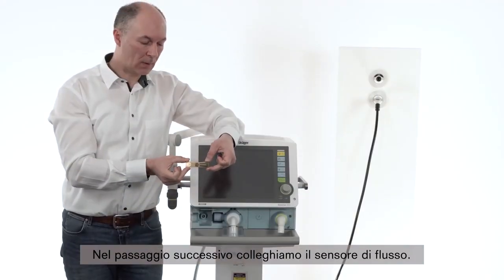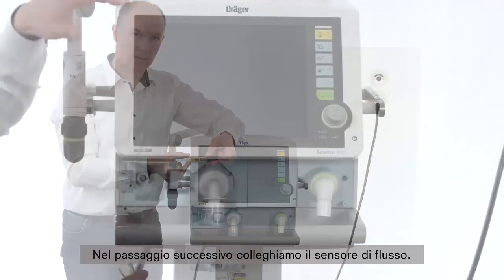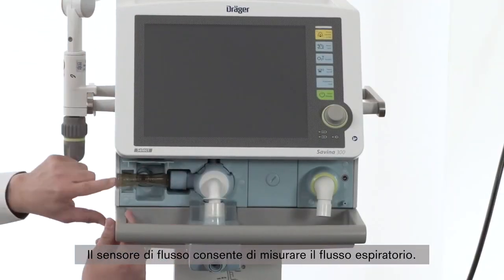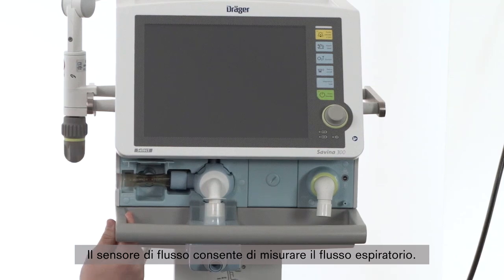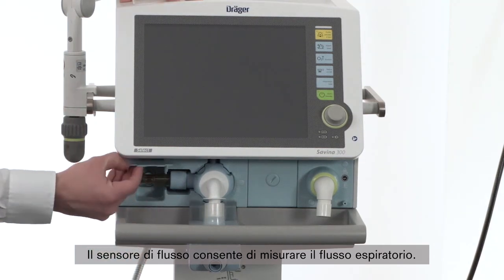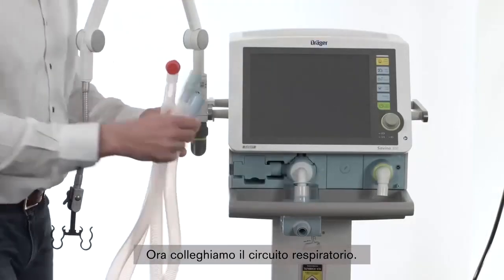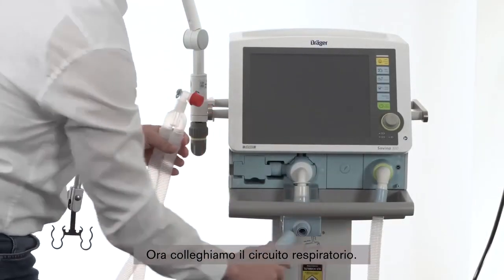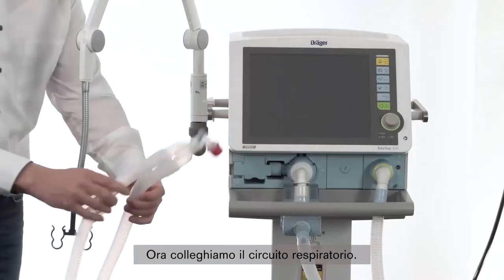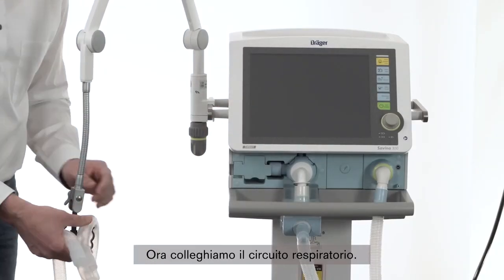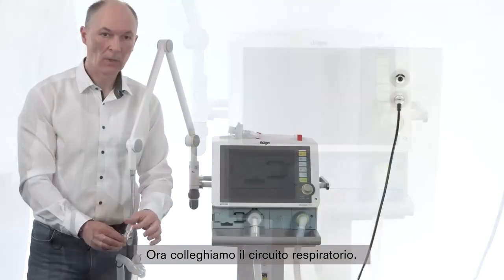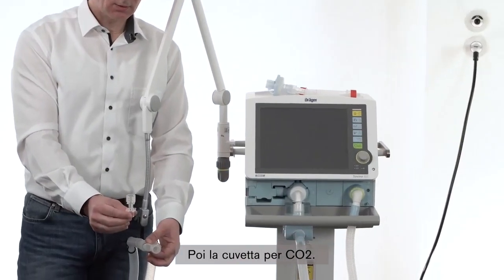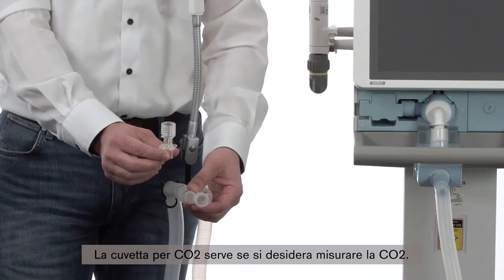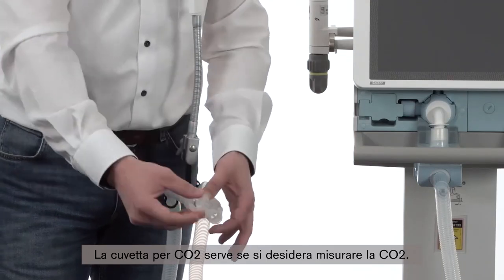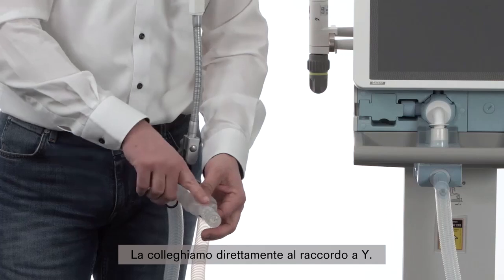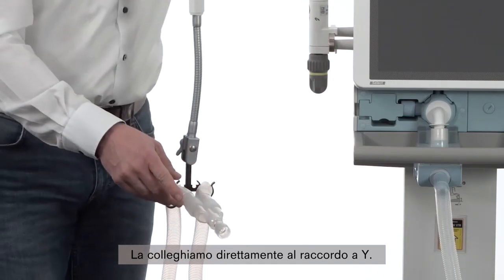In the next step, we attach the flow sensor. The flow sensor is to measure the expiratory flow. Now we are attaching the breathing system. Now we are attaching the CO2 cuvette. The CO2 cuvette is needed if you would like to use CO2 measurement. We are attaching the CO2 cuvette directly to the Y-piece.